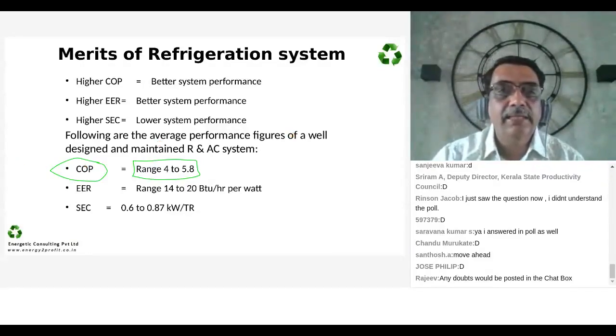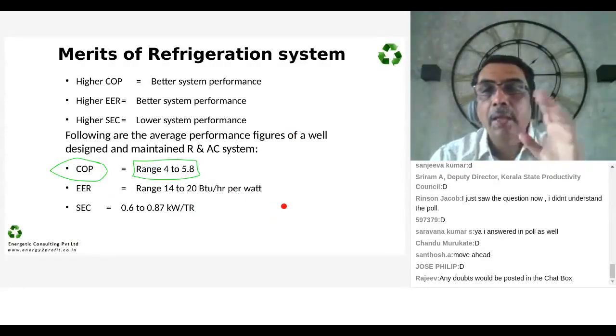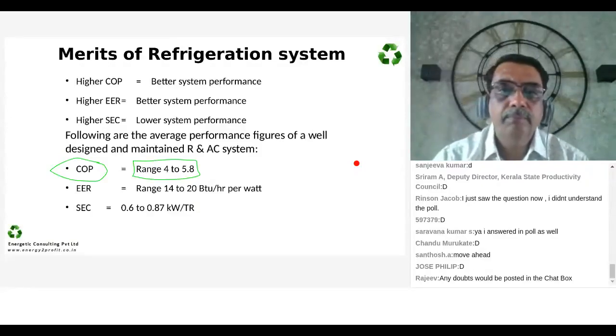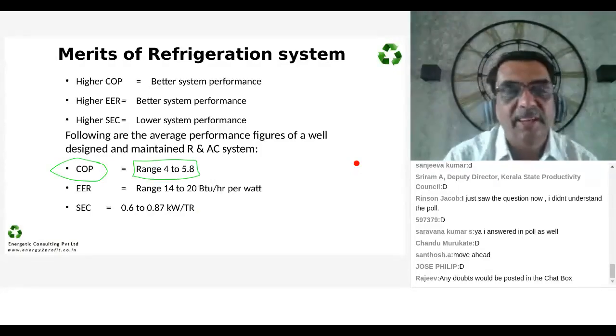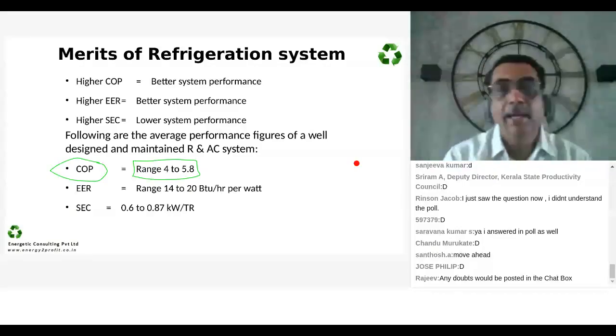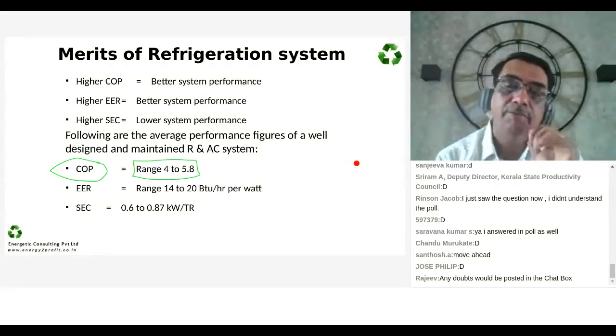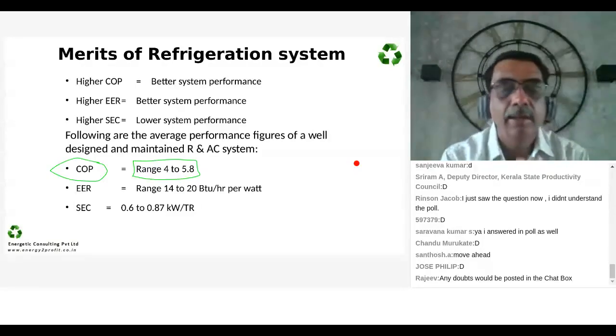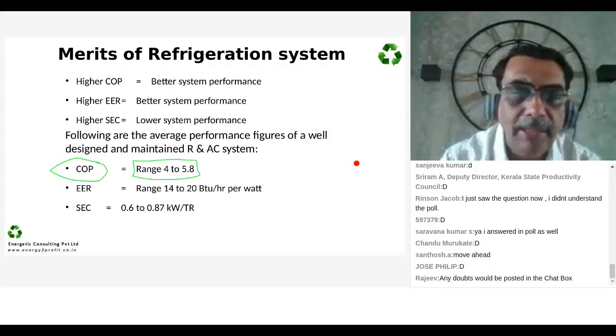Second, we have energy efficiency ratio. What does energy efficiency ratio mean? This is a formula which gives you cooling in BTU per hour. BTU per hour is the equivalent of ton refrigeration, TR, per watt of energy put in. So you are putting in 1 kilowatt, 1 watt of energy. How much cooling effect you are getting, but measured in terms of BTU or kilocalories. I mean, kilocalories is the equivalent SI unit. BTU is the unit which is popularly used. So energy efficiency ratio is BTU per hour per watt.